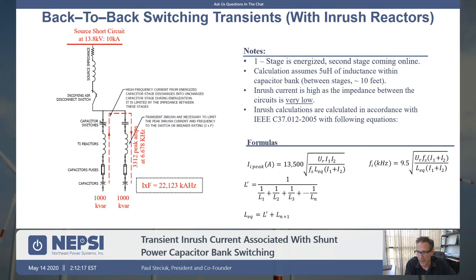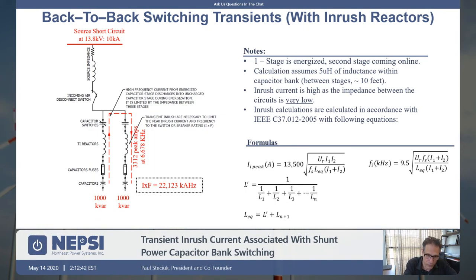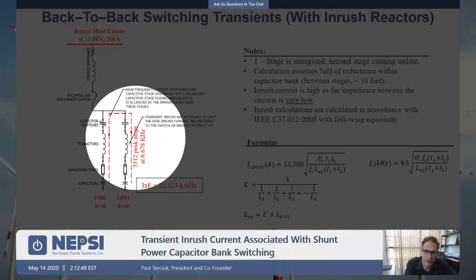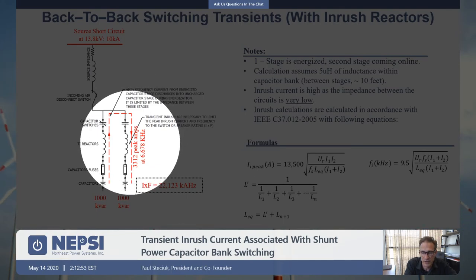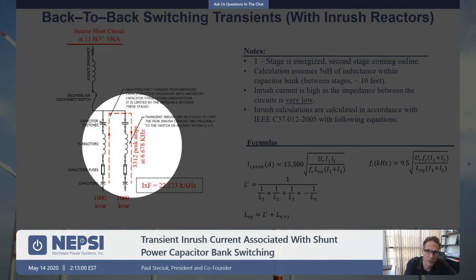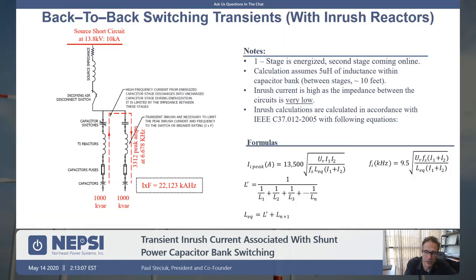It's important to keep the I×F factor, as well as the peak current and the inrush frequency, within the ratings of the switching device. The practice is to determine what value of inductance is needed to bring all three values — peak current, inrush frequency, and I×F factor — within the rating of the device.